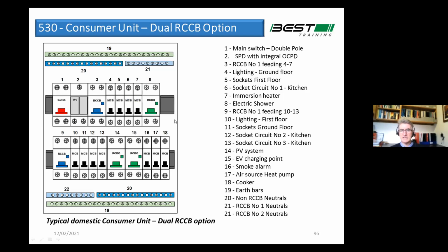So if we look through this, maybe a bit of an exaggerated approach, but this is the way that the modern house is going to go. So double pole switch again, surge protection device, dual RCCBs, several MCBs down, lights upstairs, let's say, and a few sockets downstairs, one of the kitchen circuits, and the opposite. So the other half of the sockets are here. And then we have to have some dedicated RCBOs. So what are they for? Item 8, electric shower has to be on its own RCD. You cannot put that on the sockets RCCB. So it really needs to be an RCBO, okay, on its own.